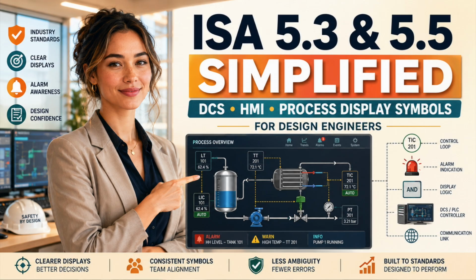At the same time, the overview should not be covered with 30 tiny permissive indicators beside every motor. Show the operating condition first, then allow the operator to open the reason. Control system symbols must also distinguish accessibility and function.